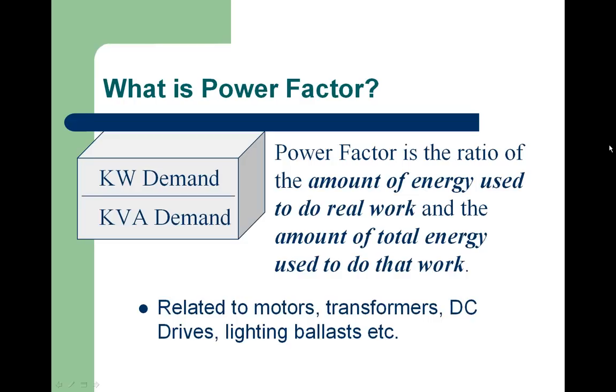As a motor is doing less work, the power factor actually decreases. For example, a 10 horsepower motor would typically have a power factor of about 83 to 85% at full load. But at half load, the power factor would be down likely into the mid-60s. And if it's a quarter loaded, 25%, the power factor could be down well into the 40s. So if you take a number of these different motors in a facility, industrial or commercial, and you start adding up low power factor motors that are lightly loaded, you end up at your facility with a power factor of likely less than 90%.